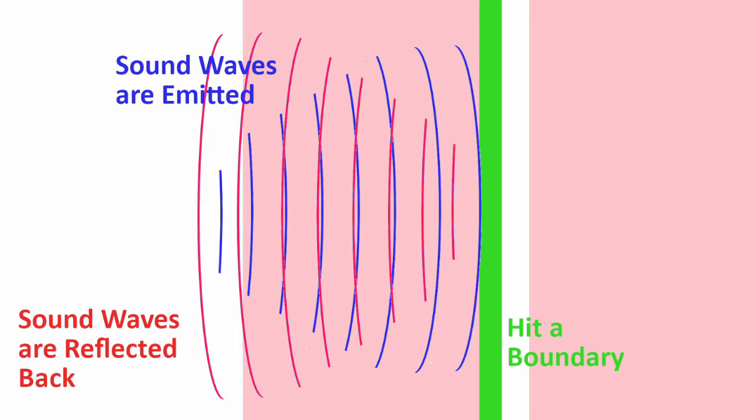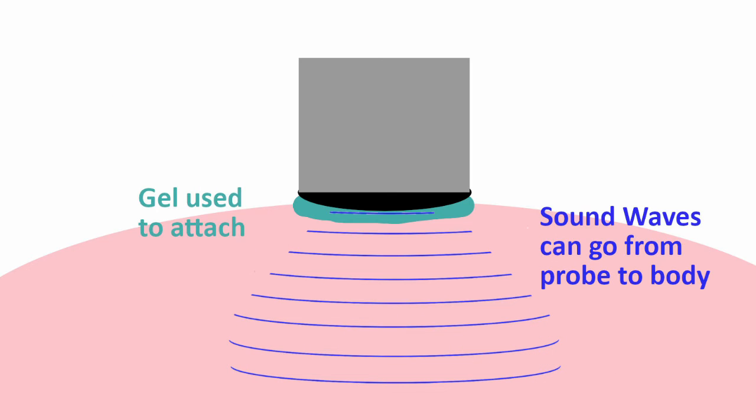This probe is coupled to the patient by a special water-based gel, which allows the sound to pass through the skin without being disrupted, along with making the probe less likely to slide, which would produce worse quality images. They then use the speed of sound in tissue, 1,540 meters per second, to determine distance and intensity of echoes, based off of time and amplitude.